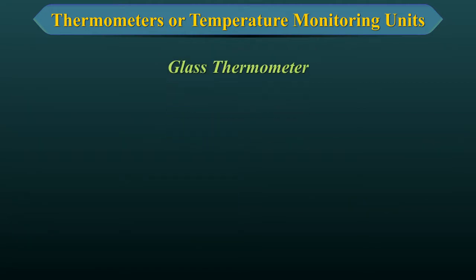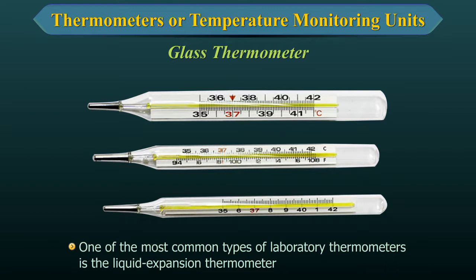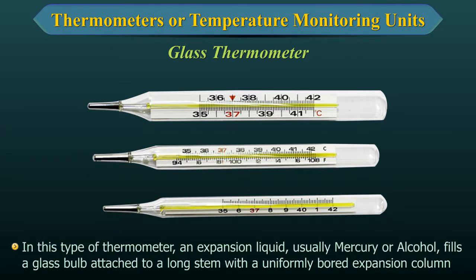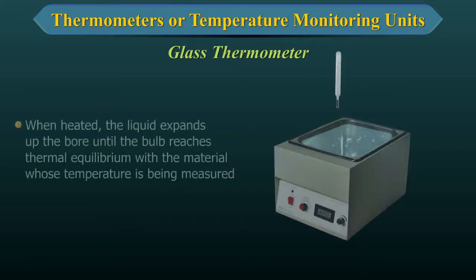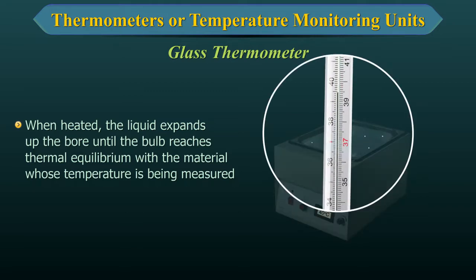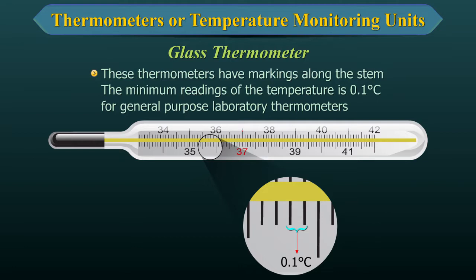Glass Thermometers. One of the most common types of laboratory thermometers is the liquid expansion thermometer. In this type of thermometer, an expansion liquid, usually mercury or alcohol, fills a glass bulb attached to a long stem with a uniformly bored expansion column. When heated, the liquid expands up the bore until the bulb reaches thermal equilibrium with the material whose temperature is being measured. These thermometers have markings along the stem; the minimum reading of temperature is 0.1 degrees Celsius for general-purpose laboratory thermometers.